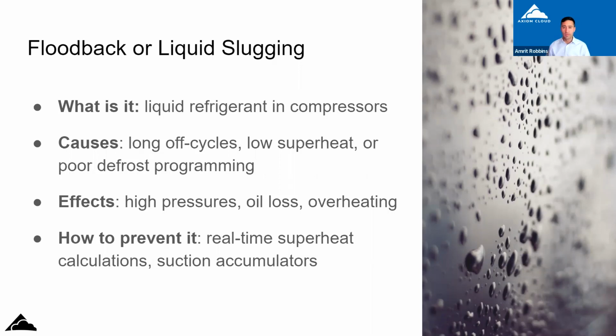And so you can start to detect those leading indicators through real-time superheat calculations, or you can avoid them entirely by installing suction line accumulators or crankcase heaters. Obviously, those are an extra layer of protection against these sorts of failures where liquid is entering the compressors. Do you guys have any thoughts on how to use data? Or I guess maybe Joe specifically, do you have thoughts on how data can be used to avoid these types of failures, floodback and liquid slugging, and better monitoring, better data, better analytics?